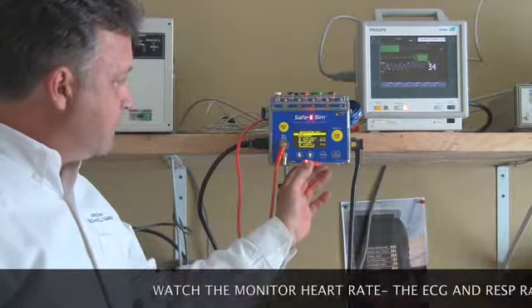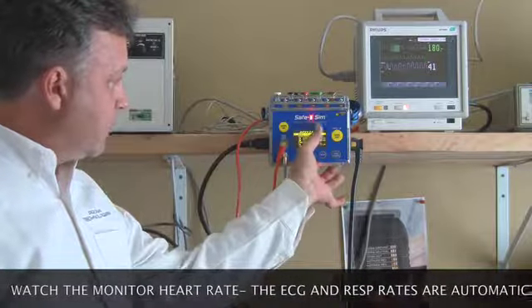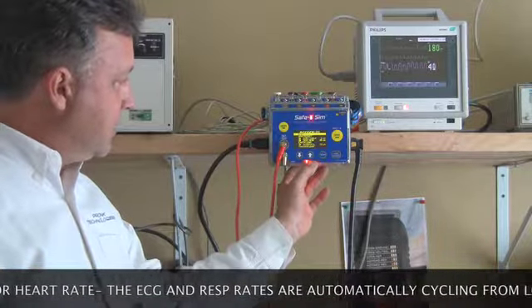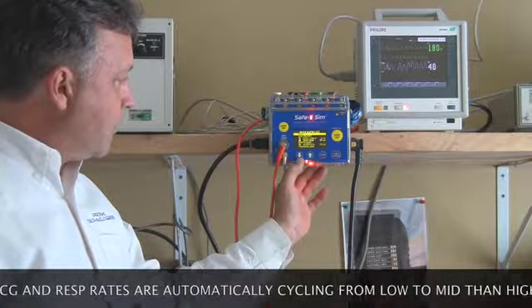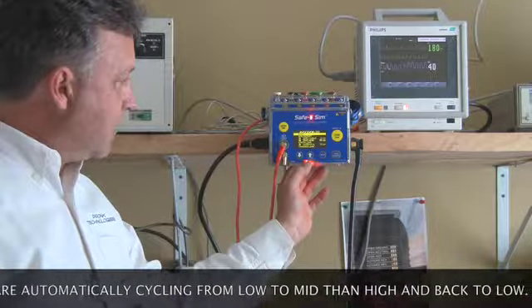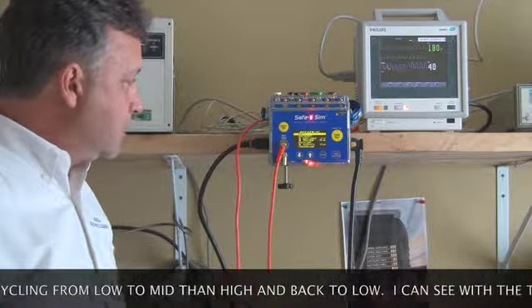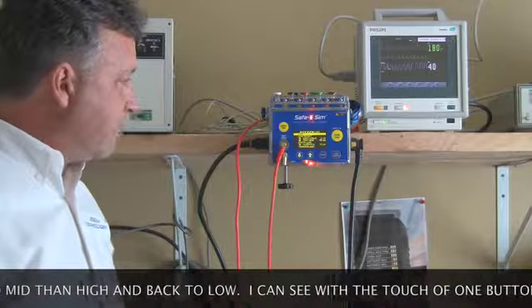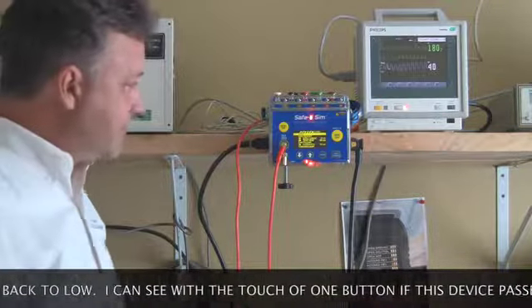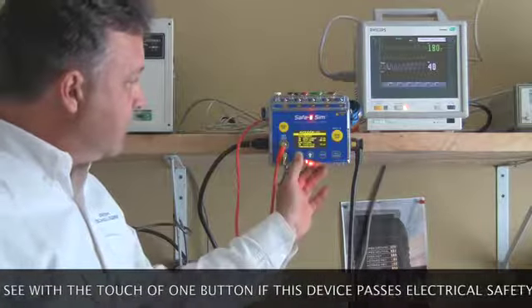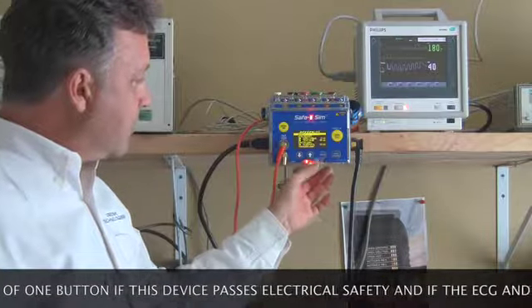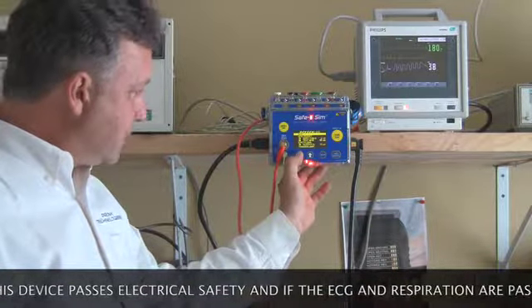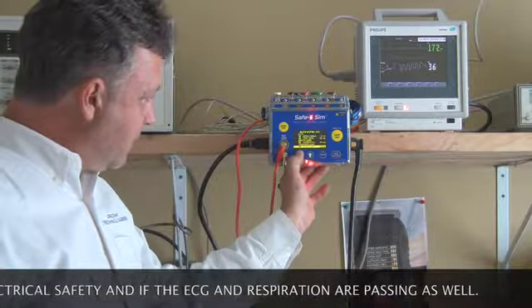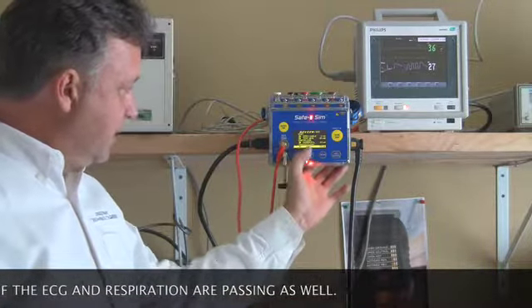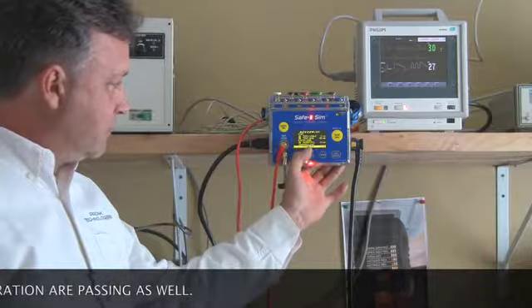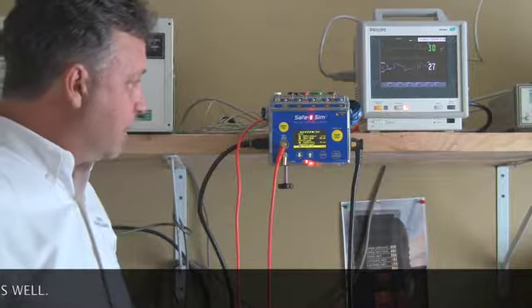One of the individual tests failed, so we've got a red LED glowing on the device in both the bottom and the top areas, so that you don't have to worry about missing a failing electrical safety test ever again. You can see it and you can hear it that something failed in that automated test. I can scroll down from there, find out which one it was. I've got a flashing F under chassis leak, normal polarity, ground open.